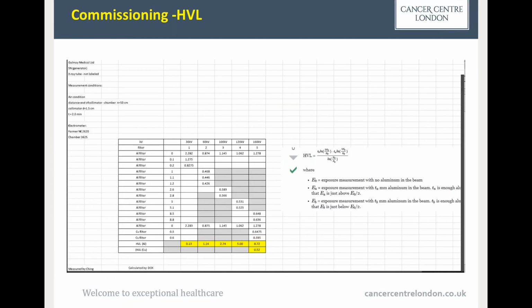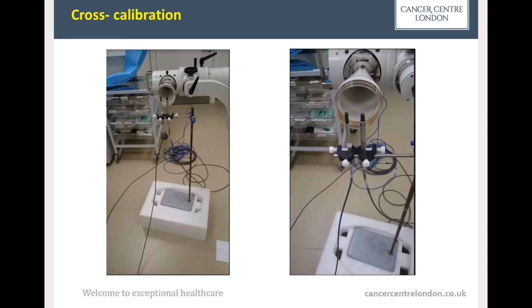And this is our table, where we have measured HVL for all energies which we have implemented here. We don't use 30 kV clinically, we use from 60 till 160 kV, but because it was commissioning, we made the decision to do everything from scratch. Having the energy, which is quite important, we could start to do intercomparison. It means we could prepare our chambers for measurements which must be done regularly afterward to check if the output for this system is stable and constant.